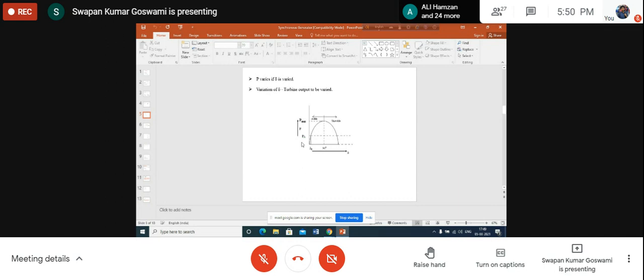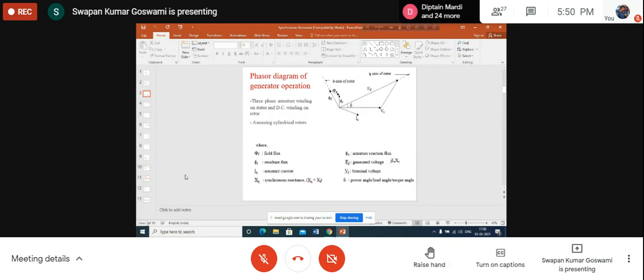Rather, directly I shall take 10 megawatt power output from the generator itself. That's why the only method of changing the active power output of the generator is to change the delta. Now, how can delta be changed? What is delta? Delta is basically the angle between the induced EMF and the terminal voltage.